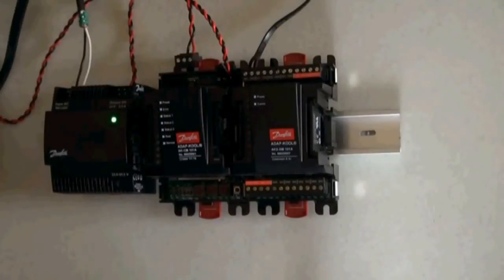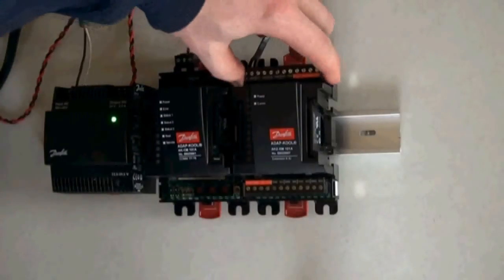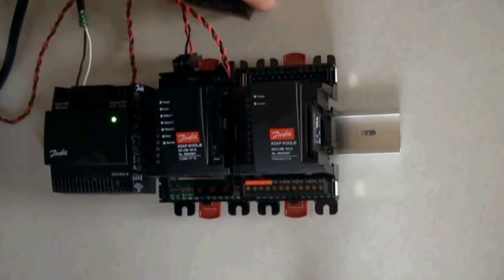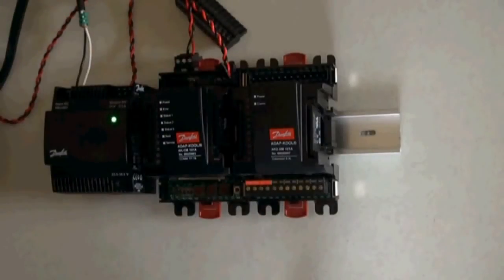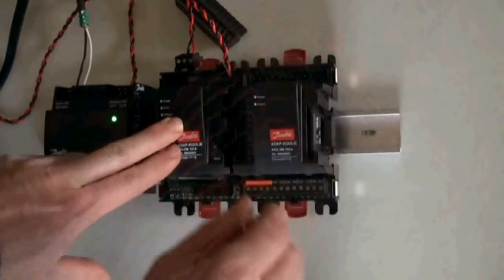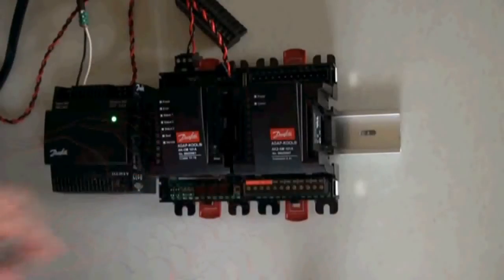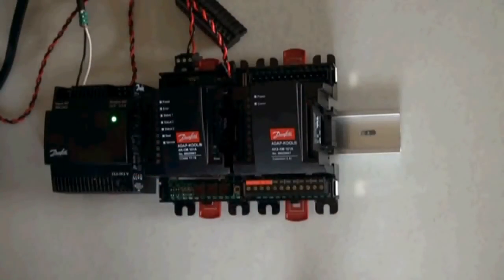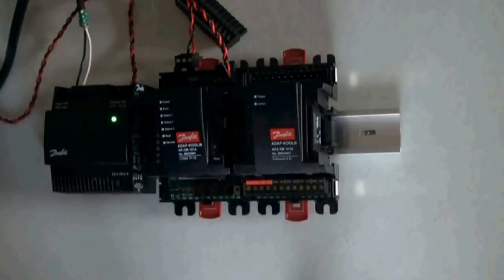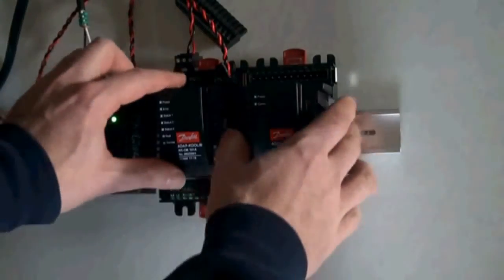First, we'll remove any connectors with wires attached. To remove the module, first we must unlock the tab from the DIN rail. First starting at the top, then the bottom. You'll note that the red tab stays in place. This indicates that the module is unlocked from the DIN rail. Next, lift the module directly toward you.